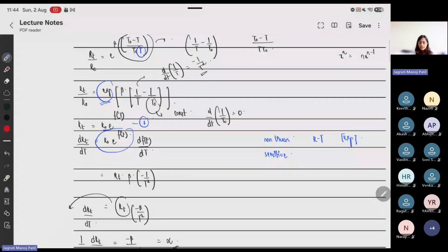Now you can achieve linearity here - how do you do so? You can have a resistance in parallel with the thermistor you're trying to measure, or you can have a resistance in series with the thermistor you're trying to measure. If you have it in parallel, you can have this as adjustable. If you had it in series, you can increase the load, and since load increases, your deviation will be minimized. Your current passing through it will also decrease, so your noise in the overall system will also decrease. So your system in a way can be linear - you can achieve linearity using this, but the system inherently is non-linear.